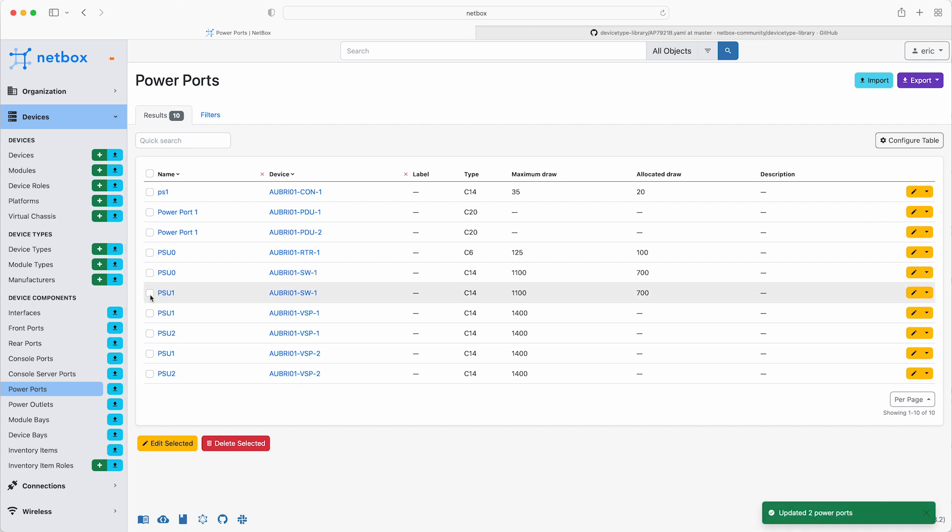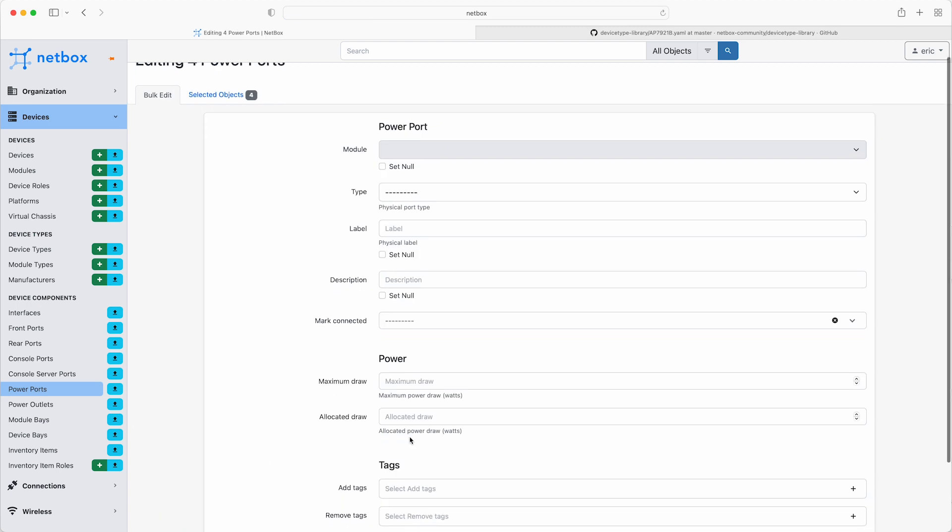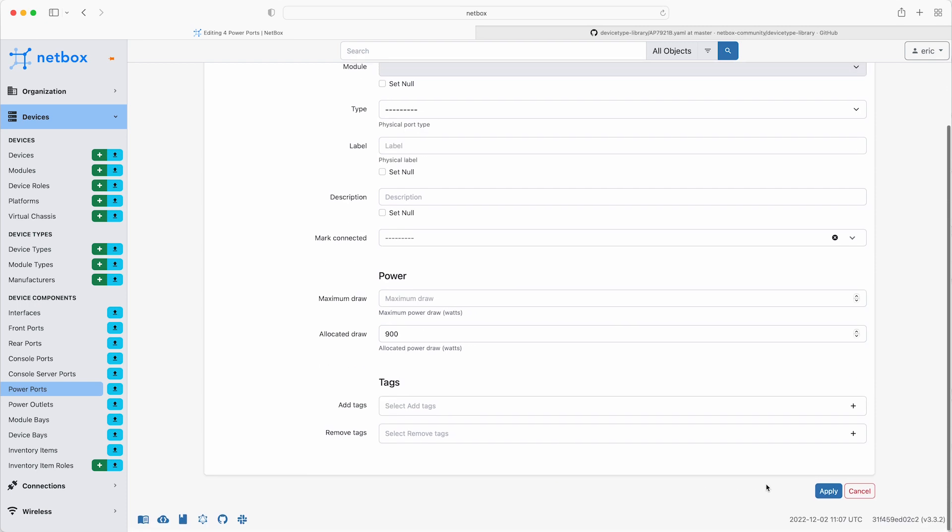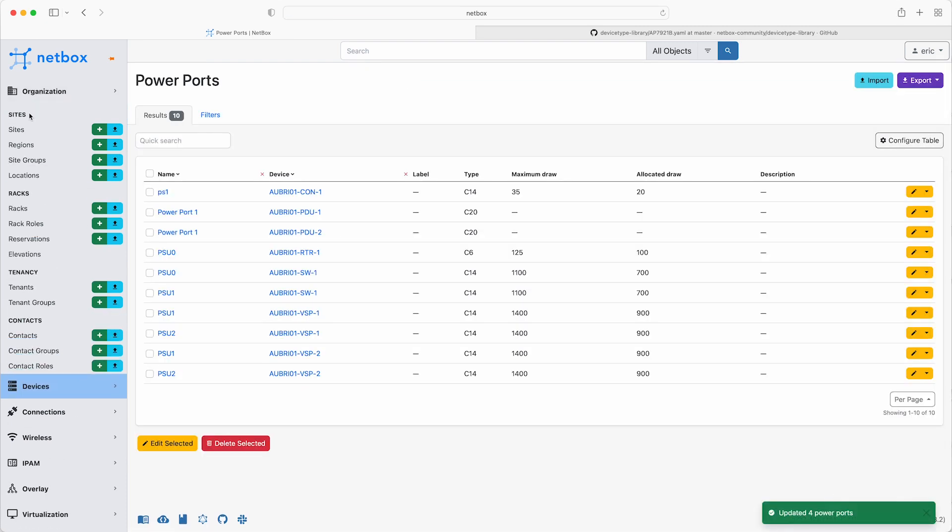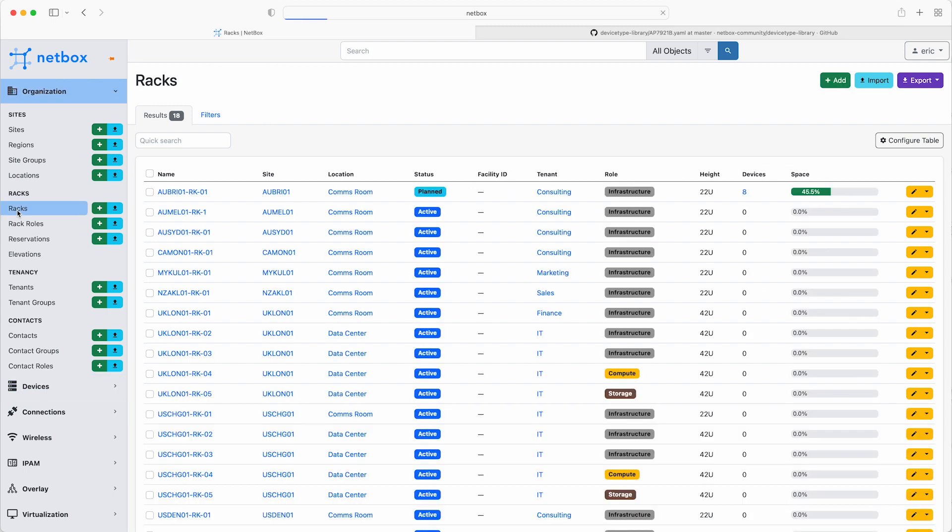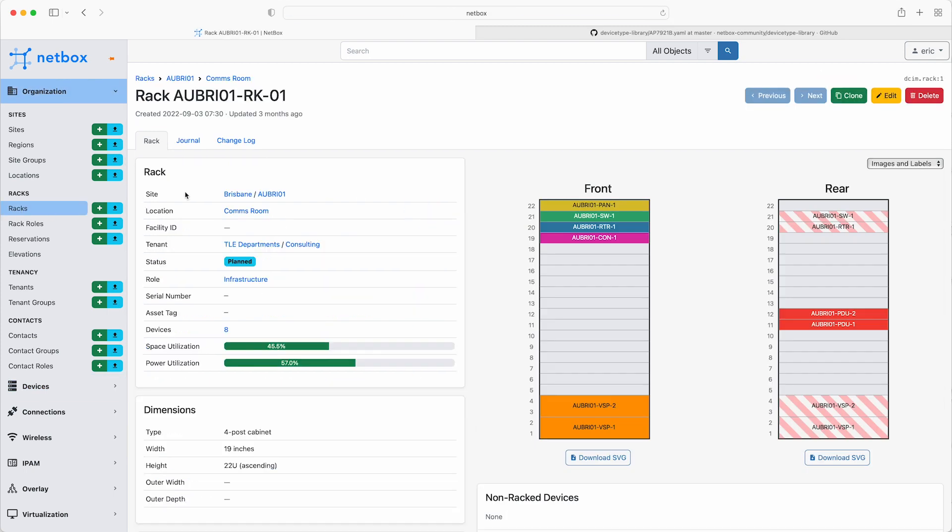Now, lastly, select all four PSUs for the servers, and set the allocated draw to 900 watts. Great, so now that's done, check the power utilisation is being tracked correctly. Under organisation, racks, and then select the Brisbane rack, and here you can see the utilisation of the available power for the rack is standing at 57%, so that's looking pretty good.